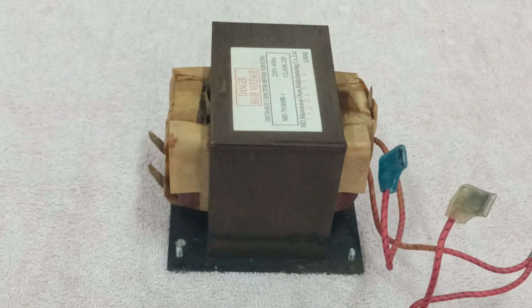Now here's a question. Is it possible to power on the high voltage transformer to test if it is indeed stepping up the voltage? Yes, that is possible. You just need to apply a very low AC voltage to the primary winding terminals of the transformer.